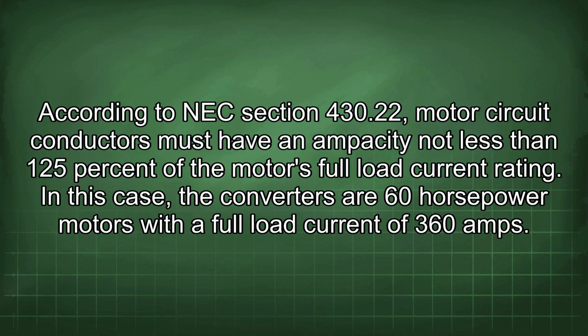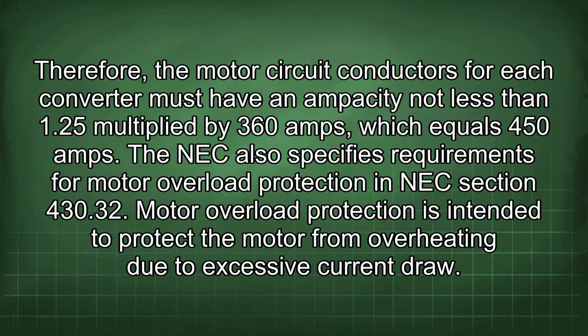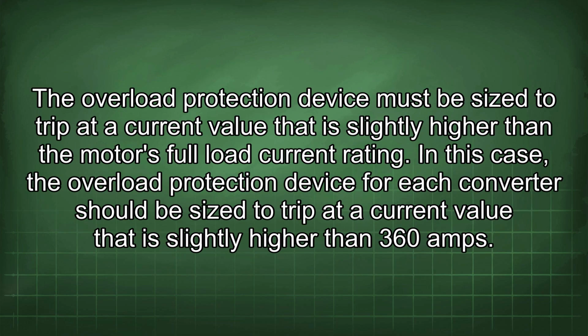In this case, the converters are 60 horsepower motors with a full load current of 360 amps. Therefore, the motor circuit conductors for each converter must have an ampacity not less than 1.25 multiplied by 360 amps, which equals 450 amps. The NEC also specifies requirements for motor overload protection in NEC Section 430.32. Motor overload protection is intended to protect the motor from overheating due to excessive current draw. The overload protection device must be sized to trip at a current value that is slightly higher than the motor's full load current rating. In this case, the overload protection device for each converter should be sized to trip at a current value that is slightly higher than 360 amps.